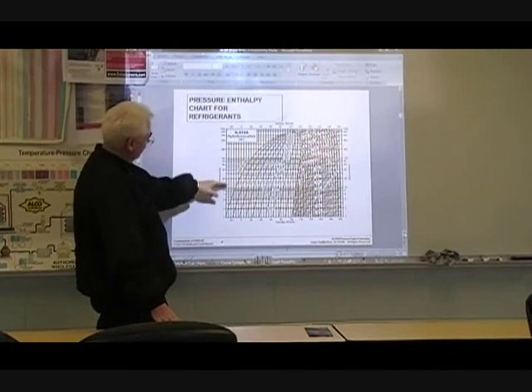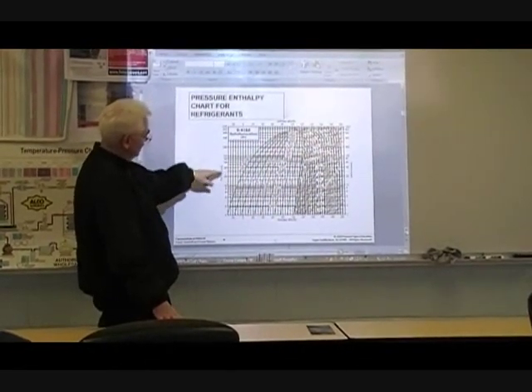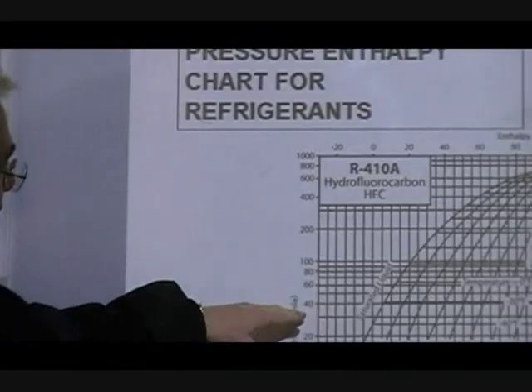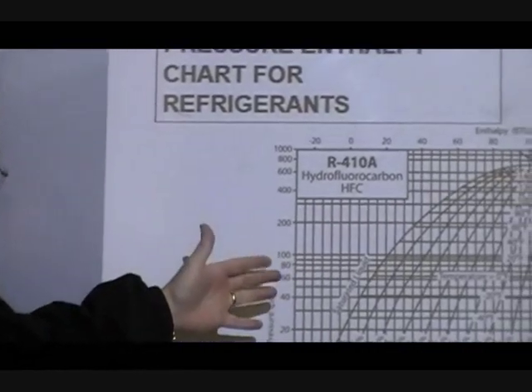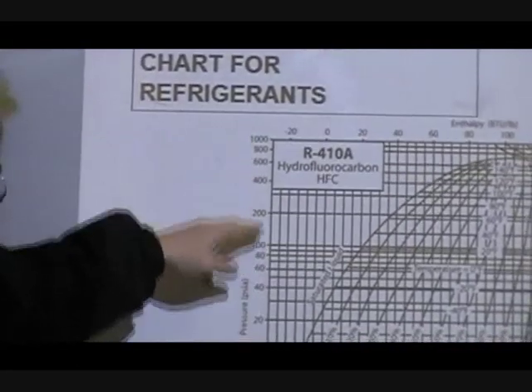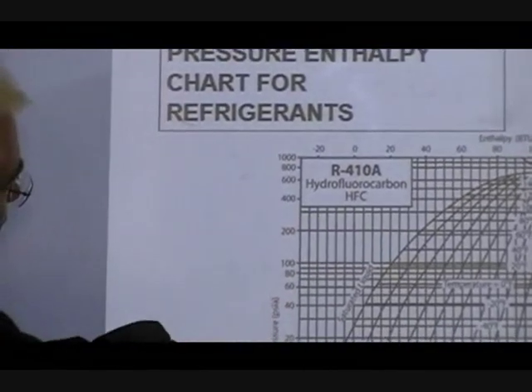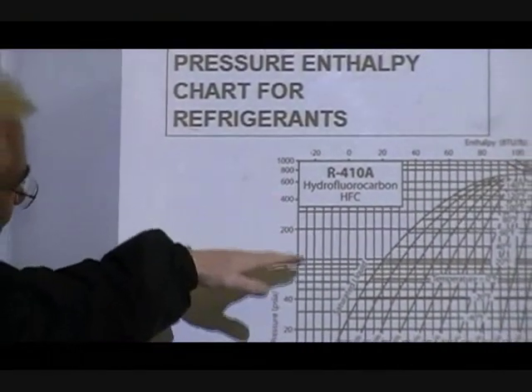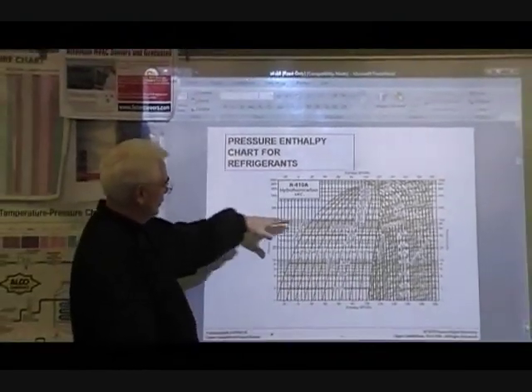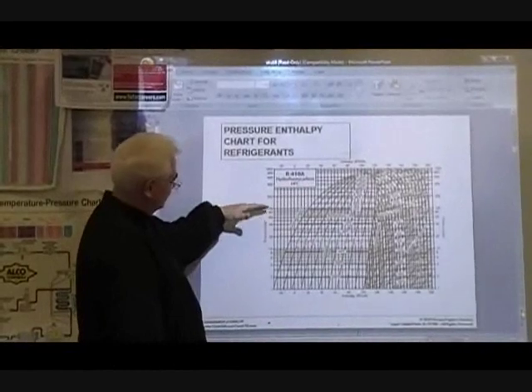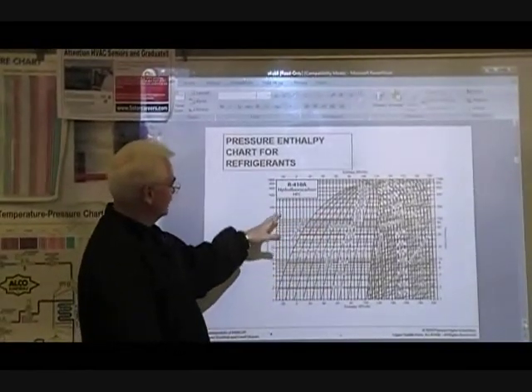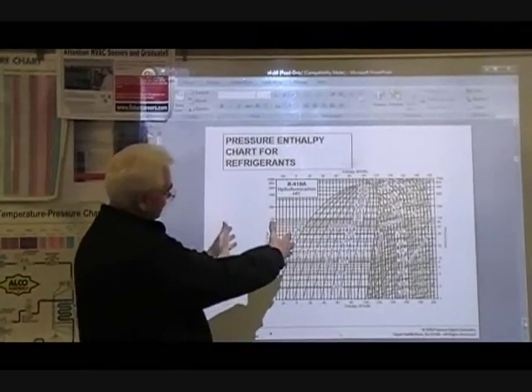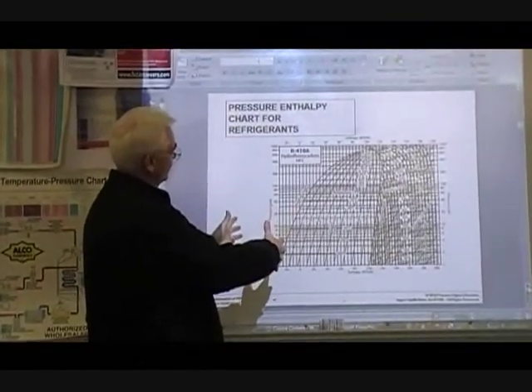The pressure columns are the horizontal graphs, and they are in absolute pressure. For example, if you've got 40 PSIA, to get gauge pressure you subtract 15, giving you 25 PSIG. Your pressure readings here are absolute. You've also got temperature readings, and for any given refrigerant you can relate pressure to a temperature correlation — so you've got a pressure-temperature chart within the pressure-enthalpy diagram.